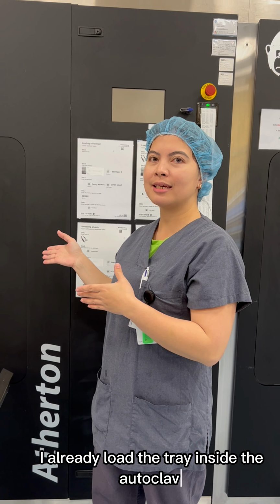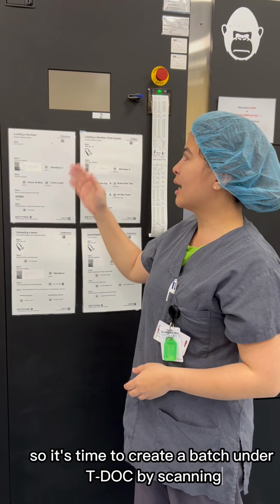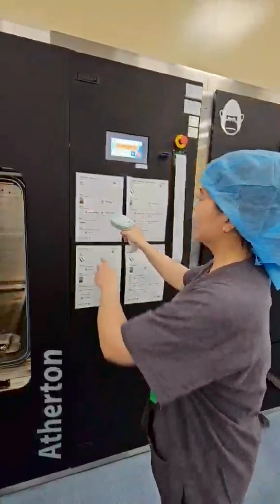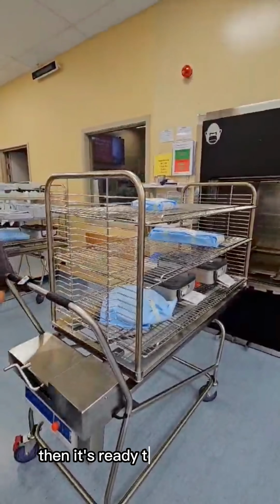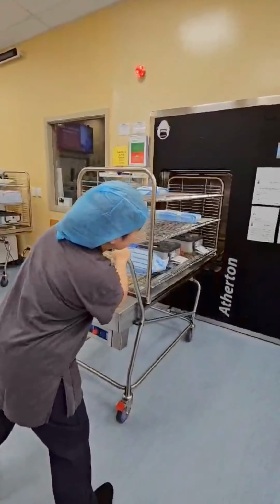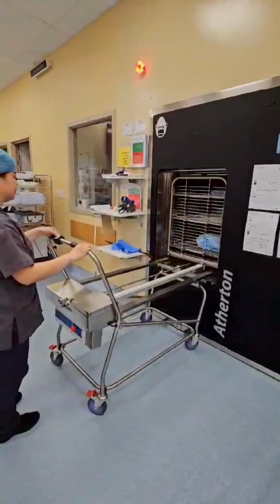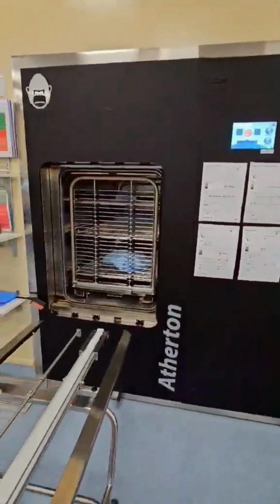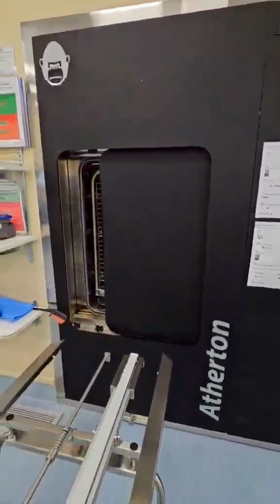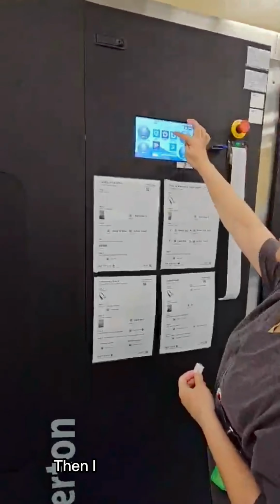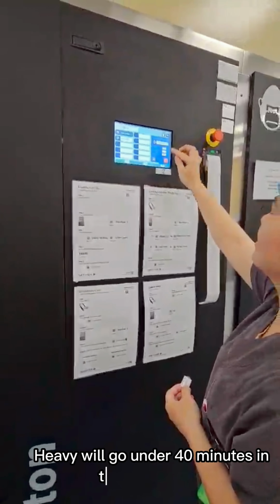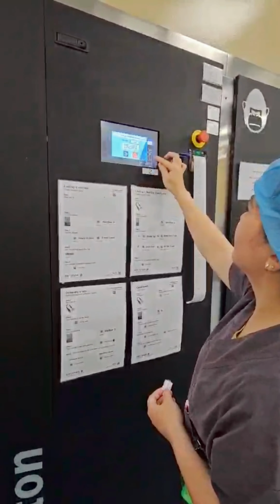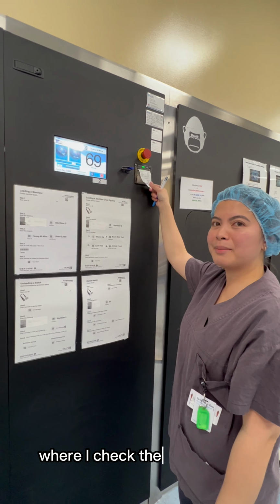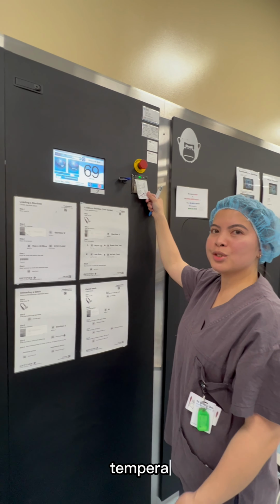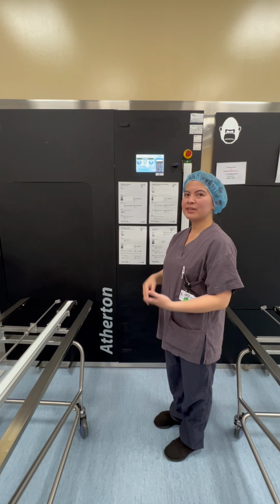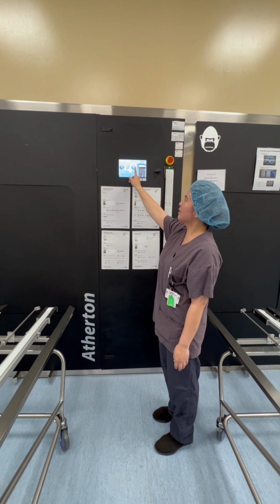I already loaded the tray inside the autoclave, so it's time to create a batch under TDoc by scanning, loading, then it's ready to load the trolley inside the autoclave. Then I choose the standard cycle, heavy, which will go under 40 minutes. And the arrow, and the enter. This is the sterilizer printout where I check the parameters of pressure, time, and temperature, and this sterilization will take 40 minutes. After the sterilization, the autoclave screen will show cycle pass, and it's time to approve.